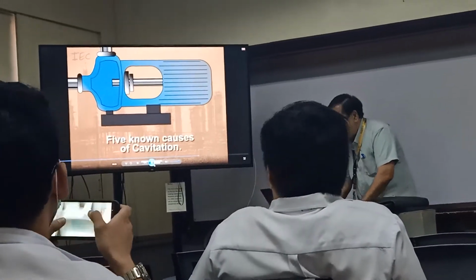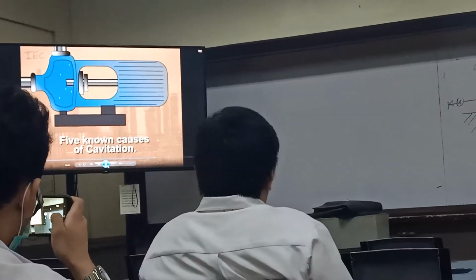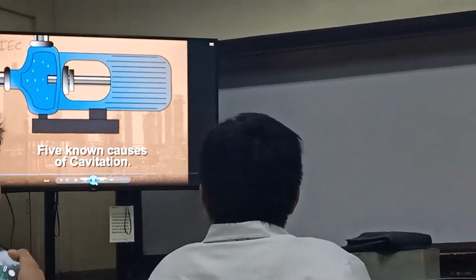There are 5 basic causes for this. Pay attention here. Vaporization, air ingestion, internal recirculation or flow slip, turbulent flow, and the vane passing syndrome.